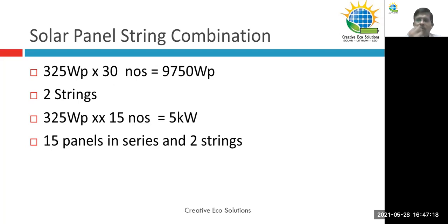Now we spoke about a 10 kilowatt system. Right? Now, in case I have a bigger plant, let's say I am designing for a 30 kilowatt system or a 50 kilowatt system, I go to that specific catalog, find out the number of MPPT trackers, the number of MPPT inputs, and what is the MPPT voltage range. Based on the voltage range, I will decide on the number of strings.